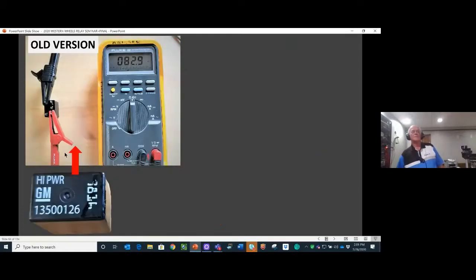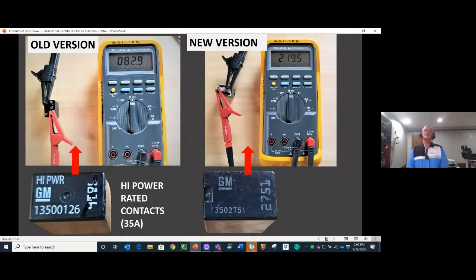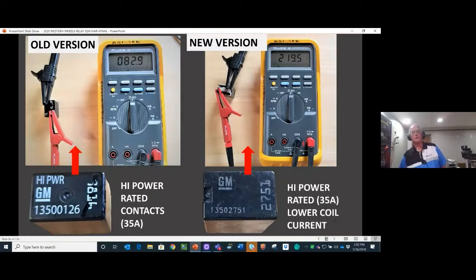So here I am with that style of relay with my trusty Fluke measuring the coil resistance. You notice it's opposite corners, and it's 82.9 ohms. These are the high rated contacts, but the standard coil resistance. Here's the new version measuring 219.5 ohms, which means lower coil current. So now you've learned about bistables and GM high power relays. Are there any questions on relay types so far? And then we'll move into diagnosis and testing.